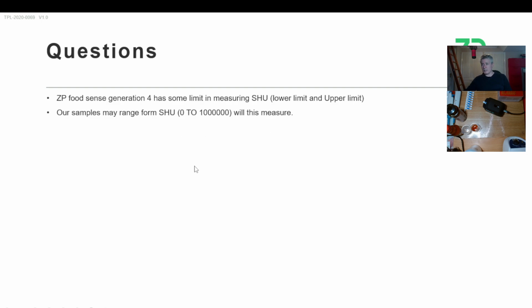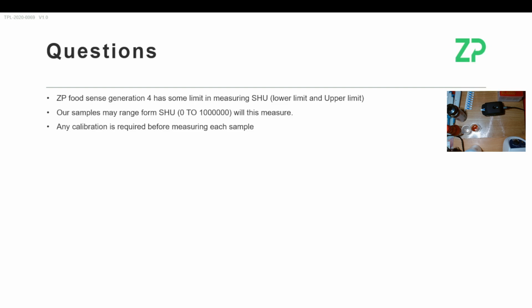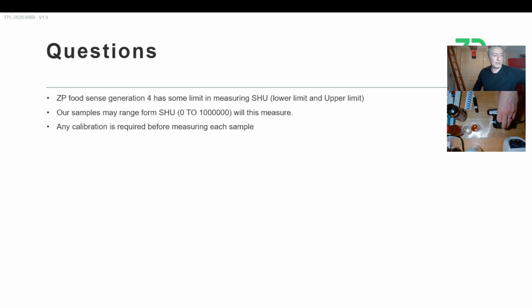1 million Scoville heat units is absolutely fine. I do say this quite a lot, and I do demos of this, that there is no calibration of this equipment required. I'm just going to turn this off for a second and grab something to indicate why we don't need any calibration of this equipment. Okay, this is a bit of a spontaneous decision, but I've just grabbed a glucose meter, and I want to lay out why we don't require any calibration.